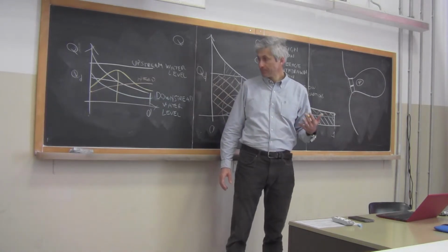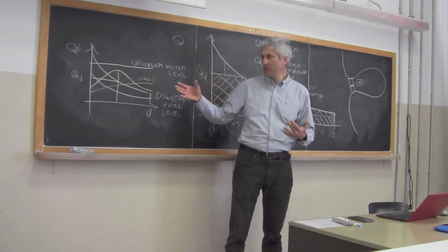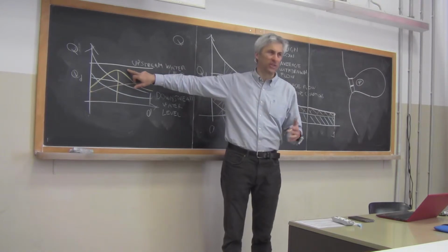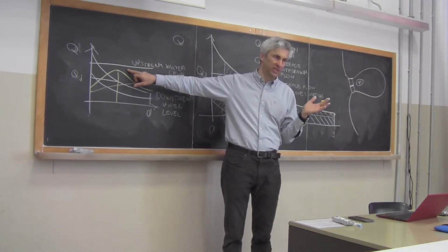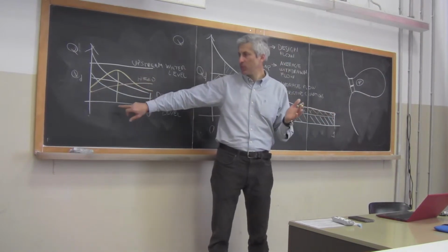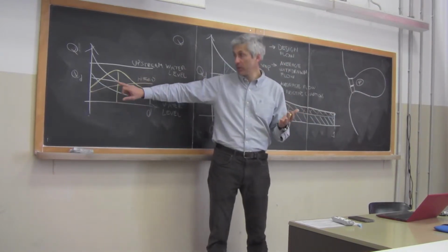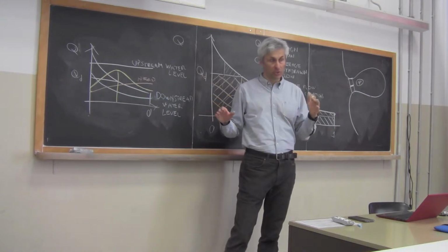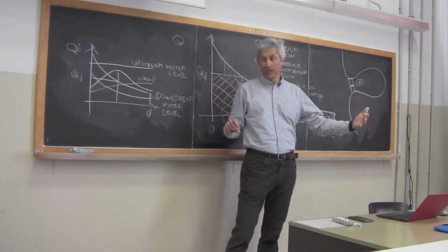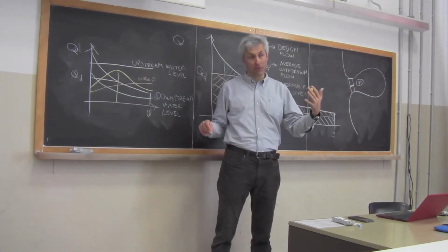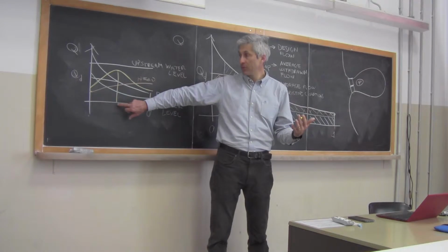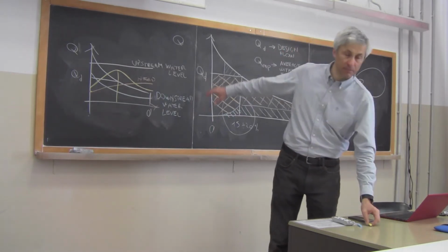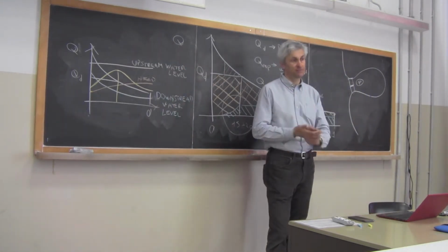And also, this figure is a bit tricky, because in the figure it's called power duration curve. I don't think we can call it a power duration curve, it's misleading. This is a curve that says for each duration, and therefore corresponding flow, what is hydropower production. But instead of saying for each duration, I prefer to say, because it's clearer, for each river flow the associated duration. Just spend some time trying to study this because it's interesting.